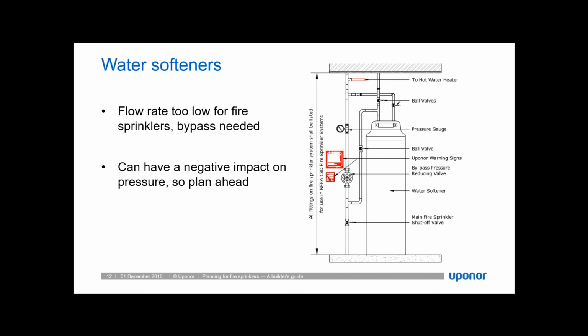The best scenario is to put your secondary pressure-reducing valve in the line going to the water softener instead of before the T that goes to the water softener. This way, the fixed loss through that pressure-reducing valve will not need to be incorporated into your sprinkler system calculations. And in that scenario, you can use a smaller and less expensive pressure-reducing valve that would have a higher fixed loss if we were having to incorporate it into our sprinkler system demand.